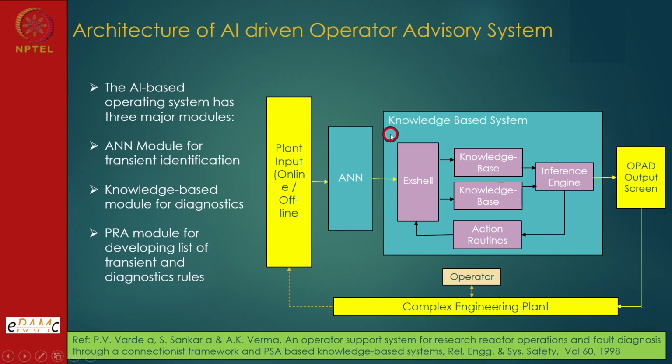If there is any deviation from the shutdown condition or safe condition, it should not take the plant into an unsafe state. So, for example, if the ANN transient was class 4 power failure or normal power failure, then after the plant has stabilized, the signal will go to do diagnostics on whether the diesel generators have started. If they have not started, what is the reason: whether it is a breaker failure, a lubricating oil failure, or some other failure.